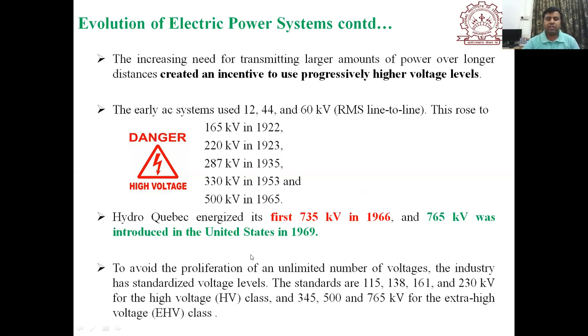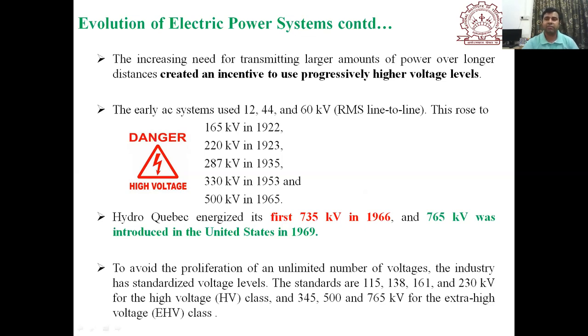To avoid an unlimited number of voltages, the industry standardized voltage levels. The standards are 115, 138, 161, and 230 kV for the high voltage class; 345, 500, and 765 kV for extra high voltage class; and beyond that for ultra high voltage. In the Indian context, high voltage lines are 33 kV, 66 kV, 132 kV, and 220 kV; extra high voltage lines are 400 kV and 765 kV; and beyond that is ultra high voltage.